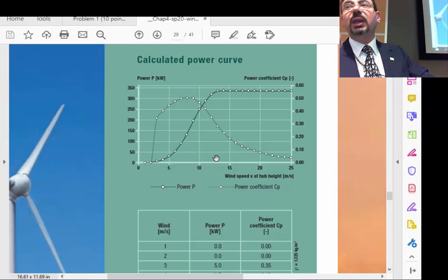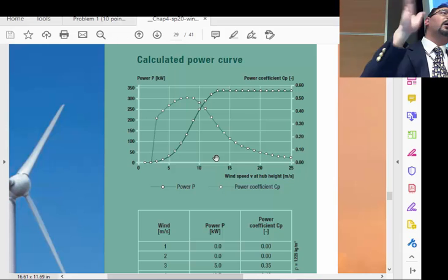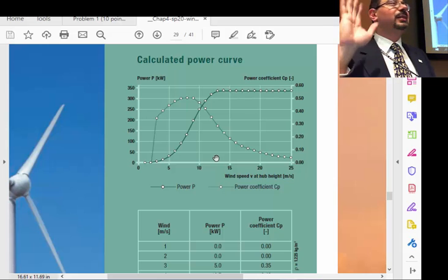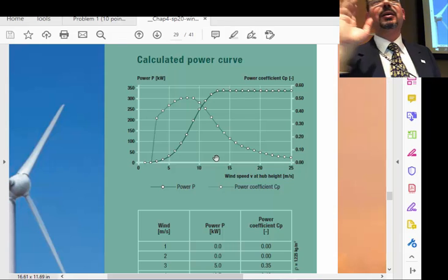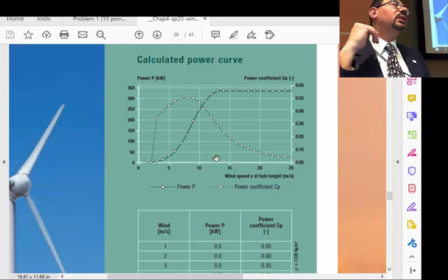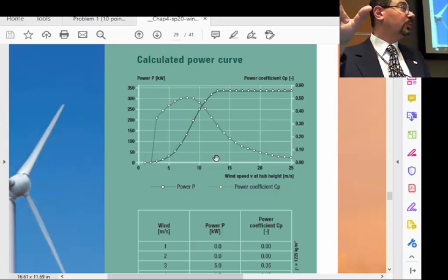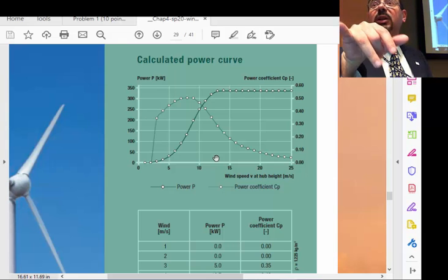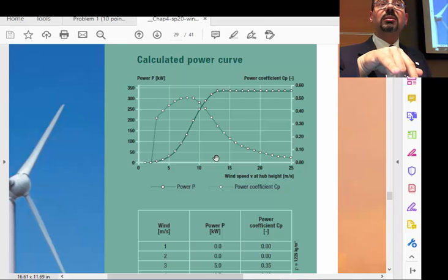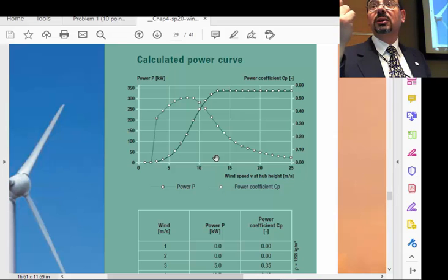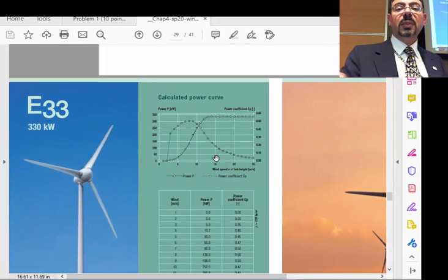You figure out how much money you make from that turbine per year, and you neglect maintenance, like this thing is running for free basically. But that's the minimum number of years in which you will get your money back. How much output you get, megawatt, times the hours where it will maintain that megawatt, times the price per unit that you are selling.